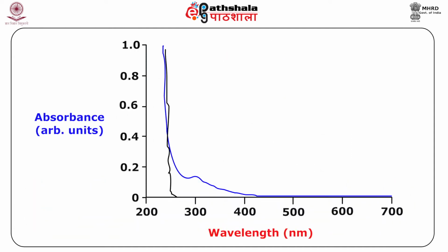Most spectrometers show absorbance on the vertical axis, and the normally detected range is from 0, that is 100% transmittance, to 2, that is 1% transmittance. Lambda max is denoted as the wavelength for maximum absorbance. Various components exhibit different absorbance and distinct absorption maxima.